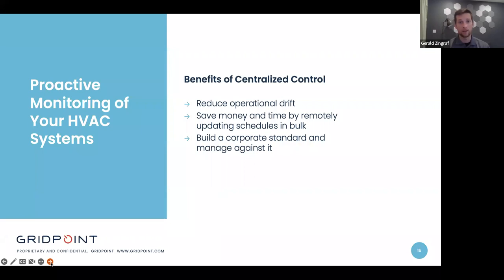If somebody adjusts the set point and you have one thermostat trying to cool to 72 and another thermostat cooling to 68, so the other one's not kicking on at all, that contributes to operational drift. This kind of stuff happens across the board. Having centralized control helps you, number one, identify when these kinds of issues pop up, when operational drift starts to rear its ugly head. And then secondly, make a bulk update, make an adjustment to move back to corporate standards.